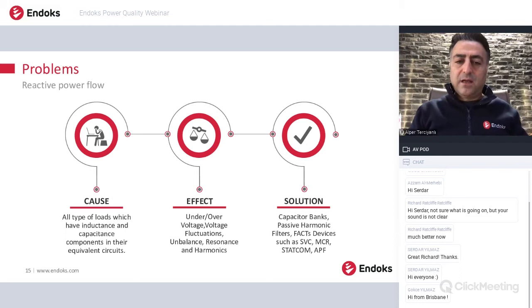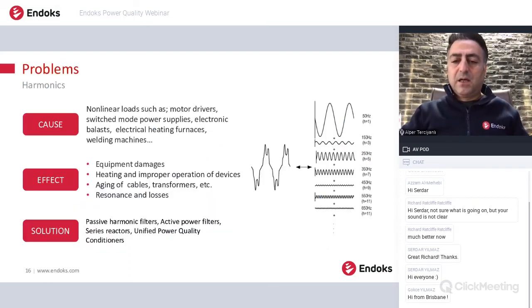So these are the causes and the effects of reactive power: under voltage, over voltage, voltage fluctuations, unbalance. Of course, there's an unbalance if the reactive power is also unbalanced, and resonance and harmonics are also effects of these reactive power problems, because at the end of the day, in order to avoid the reactive power flow, we mostly use cap banks, and these cap banks, on the other hand, generate harmonic problems if there are harmonics on the power system. To avoid reactive power flow, we use cap banks, passive harmonic filters, and FACTS devices like SVCs, MCRs, STATCOMs, or active power filters. As I said, the reactive power flow is one of the important parameters in the system with harmonics.